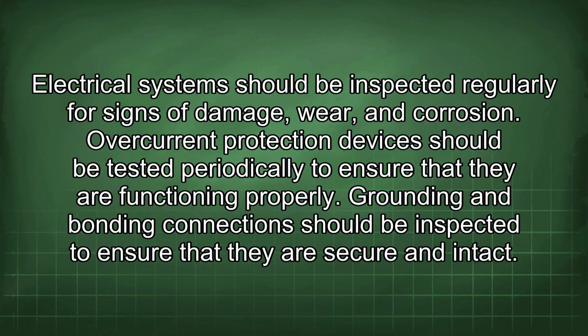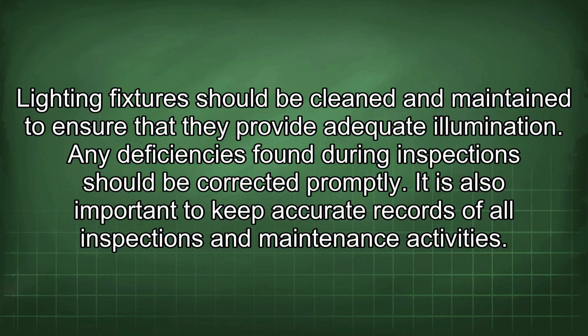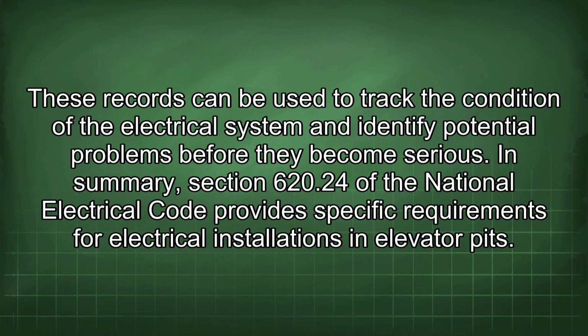Grounding and bonding connections should be inspected to ensure that they are secure and intact. Lighting fixtures should be cleaned and maintained to ensure that they provide adequate illumination. Any deficiencies found during inspection should be corrected promptly. It is also important to keep accurate records of all inspections and maintenance activities. These records can be used to track the condition of the electrical system and identify potential problems before they become serious. In summary, Section 620.24 of the National Electrical Code provides specific requirements for electrical installations in elevator pits.